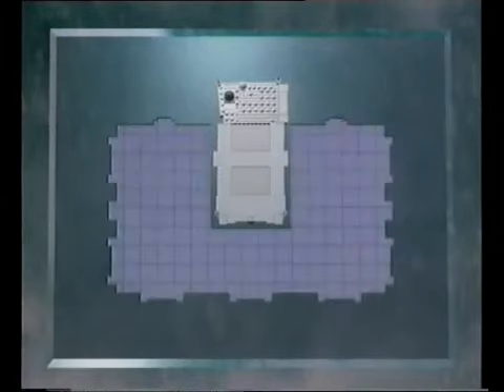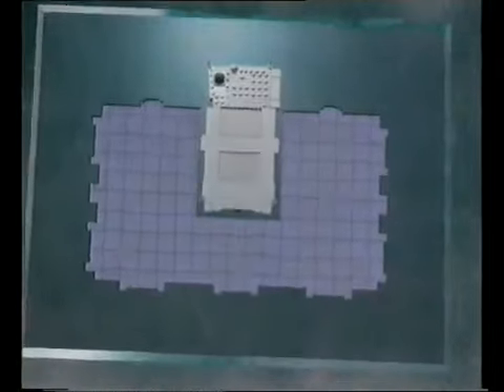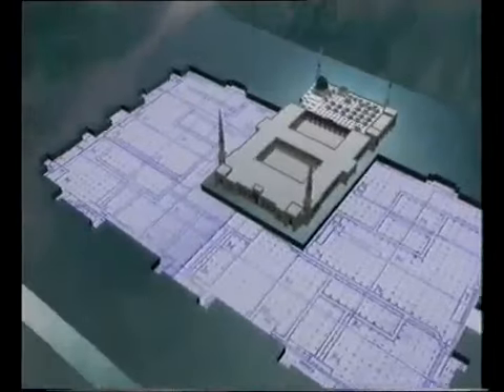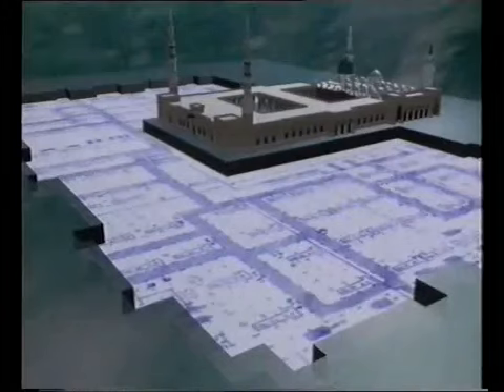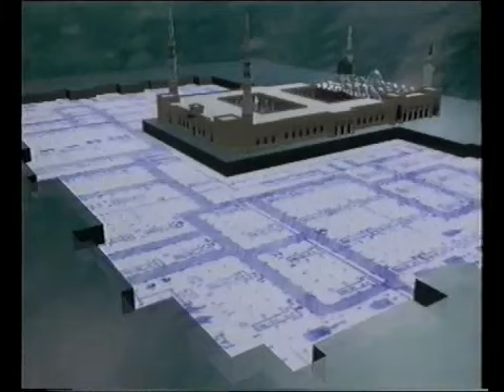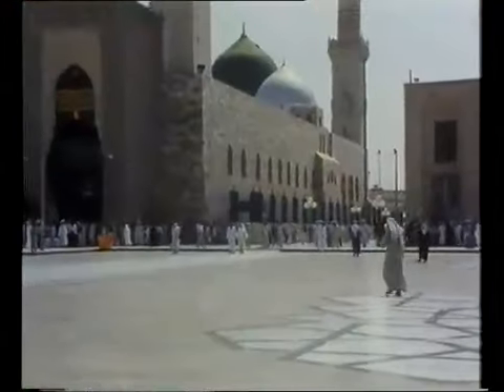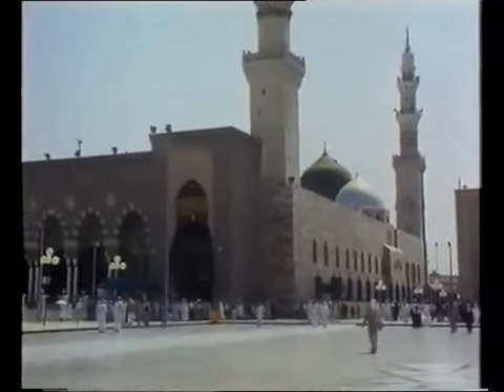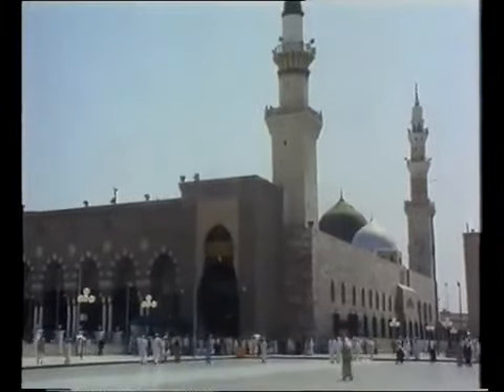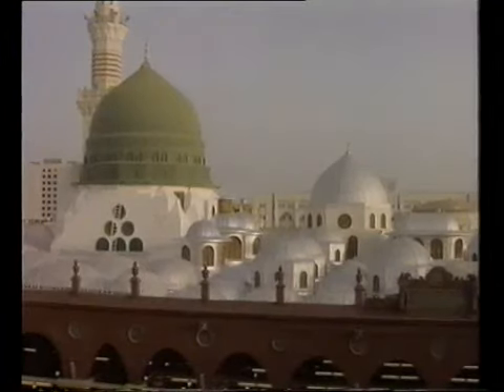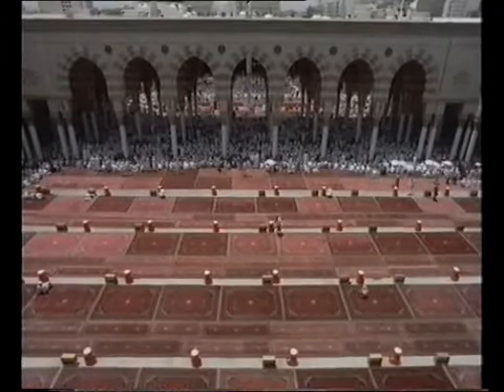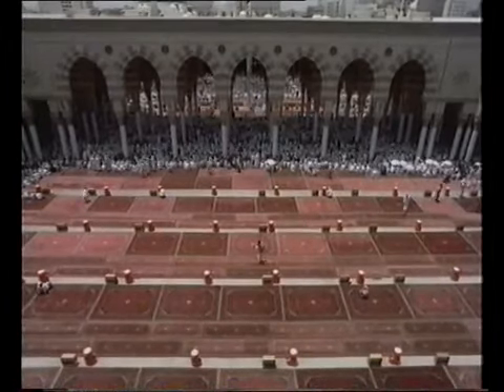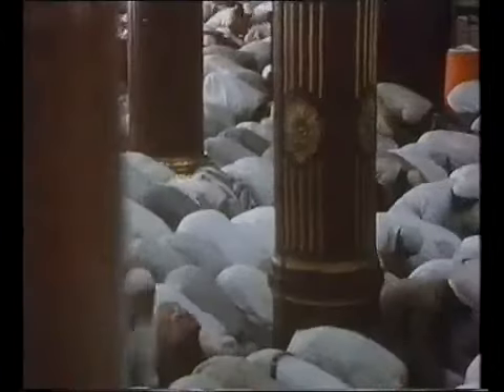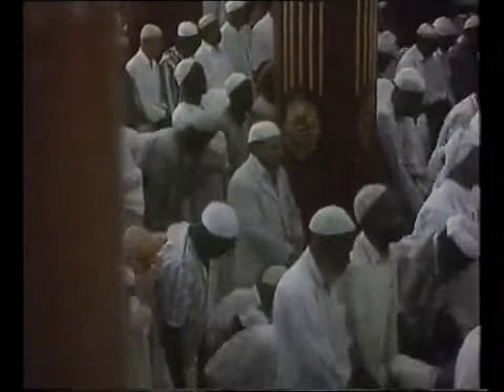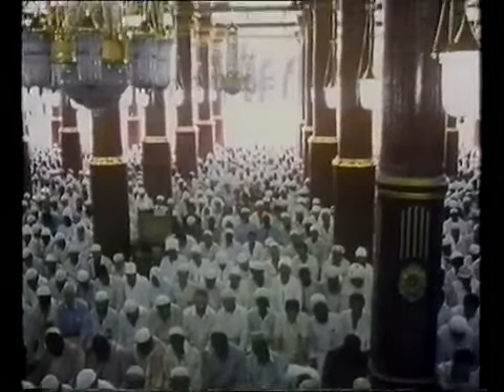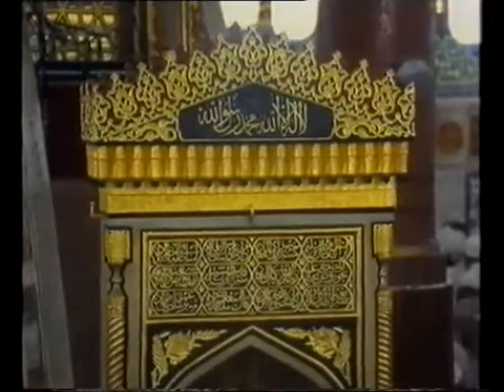The new extension around the existing mosque would increase the size of the building fivefold to 82,000 square meters, enabling the project's engineers to incorporate the air conditioning system into the initial designs of the building. Integrating the climatic control equipment into the two other existing areas of the mosque would be a more challenging and demanding assignment. Successful regulation of the temperature within the Haram was dependent on the enclosure of all areas of the building, including the two large open courtyards of the King Abdul Aziz extension. Likewise, the installation of the ducting, vents and equipment for the air conditioning system had to be done without destroying the tradition and character of the existing mosque.